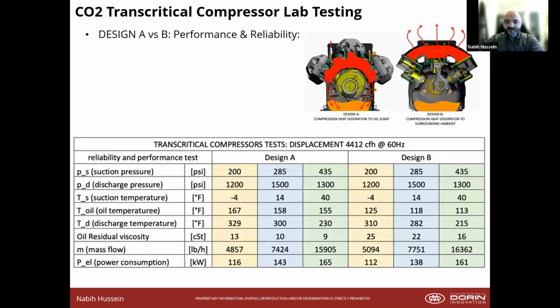And here you see the results of the comparison of performance and reliability. The most important thing is to notice your oil temperatures: 167, 158, 155 with the internal discharge plenum. You're much cooler with an external discharge plenum: 125, 118, 113. It might seem intuitive, so why did you have to check? Well, you need to validate designs, but this compressor with an external discharge manifold has the ability to keep cooler oil, which leads to residual viscosity of the oil being higher. That leads to more reliability because that oil is lubricating the internals. So that's the thought process with CO2 compressors. It's always about what we can do to make sure that these harsh conditions of high temperature, high pressure, and oil are maintained so the compressor will continue to function.